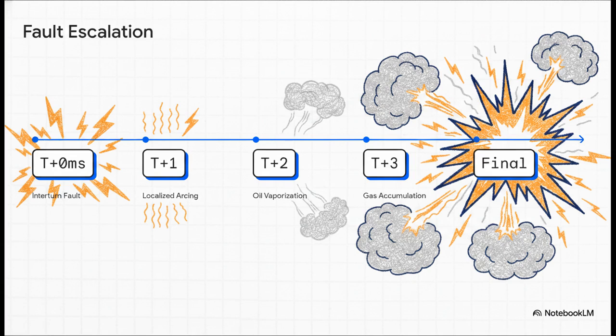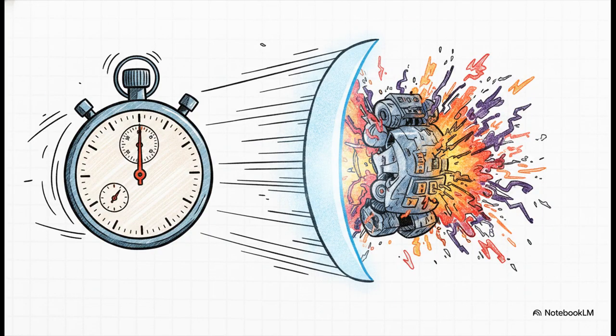First, you get the interturn fault. The heat from that causes localized arcing. Then, that arcing gets so hot, it physically vaporizes the surrounding transformer oil. That vaporized oil turns into combustible gases, which accumulate incredibly fast. They build up this immense mechanical pressure inside the sealed unit, forcing the heavy steel tank to bulge and eventually violently rupture. So, yeah, this is not just an electrical nuisance. It is a direct precursor to explosions and serious fires. Literally, the only thing standing between a minor fixable fault and a totally destroyed transformer is speed.